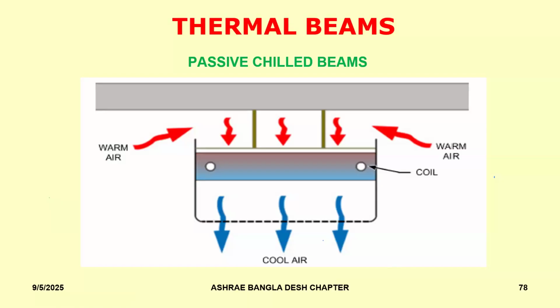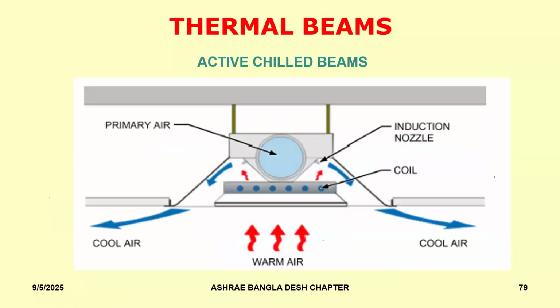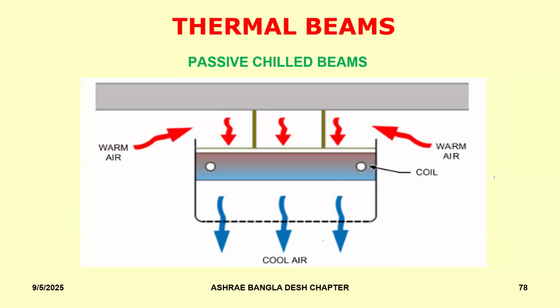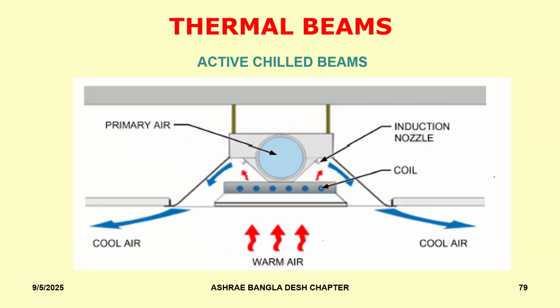This is extremely good when we want to make sure that people are comfortable without any drafts, especially if you're using the space for, let's say, a playing area like badminton, where you don't want the shuttle to be moving around because of the air velocities. The only drawback here is, as you can see, there is no way by which we can get any outside air in. So to overcome that, we have something called the active chilled beam.